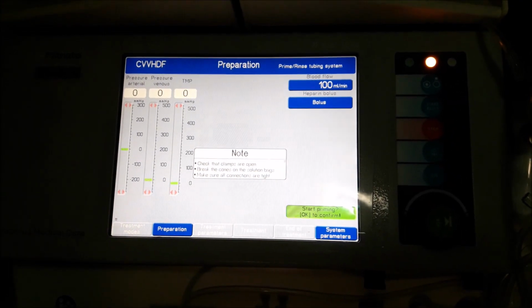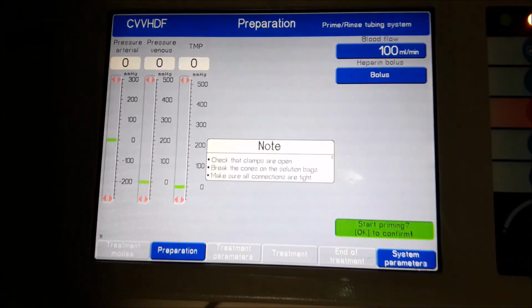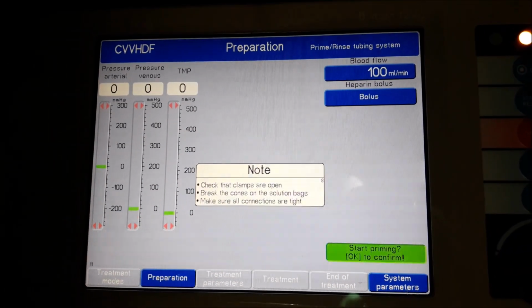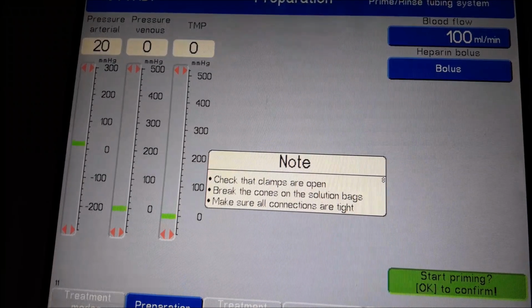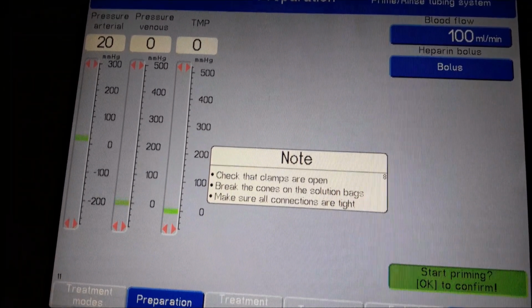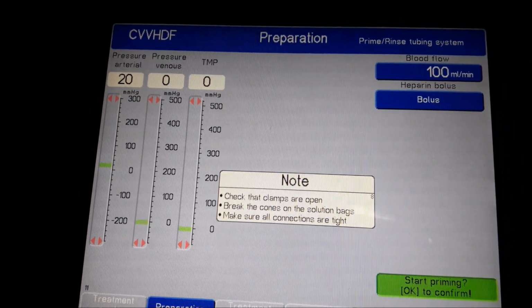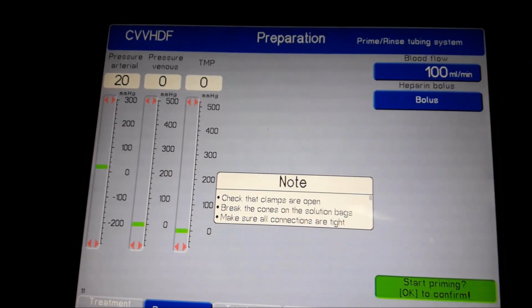Before priming, the machine is giving us a note. First point is check that clamps are open. We have already opened all the clamps. Second point is break the cones on the solution bags. Let's move toward the solution bags which are present at the back side of the machine.